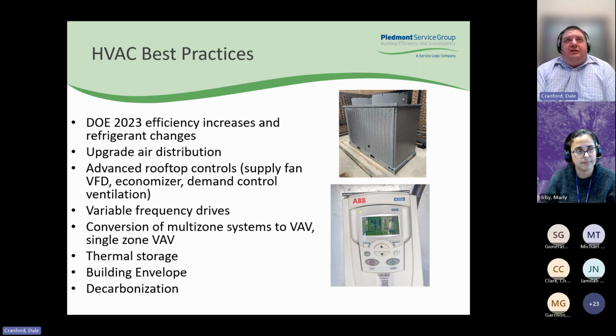Looking to upgrade air distribution. A lot of the older type systems with dual duct and multi-zone systems, we can convert those to more of a VAV operation with reheat that's more dedicated to specific zones rather than doing heating and cooling at the same time. Looking at things like advanced rooftop controls. A lot of rooftop units now can come with supply fan VFD, outside air economizer, and demand control ventilation. So using CO2 to reduce the amount of outside air when it's favorable, and to increase it when there's a lot of people in a space.